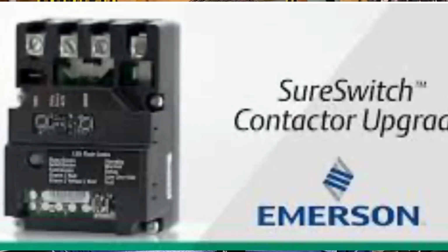In fact, if I were going to put in a new zoning system today and the system was using an old style contactor, I'd probably replace it and put in some kind of Emerson Sure Switch or equivalent, so at least it would last a little bit longer. Switches like the Sure Switch kind of cut down on the electrical issues you have when you're starting and stopping the system, therefore they'll last a whole lot longer. They also have some diagnostic capabilities depending on which ones you're choosing.